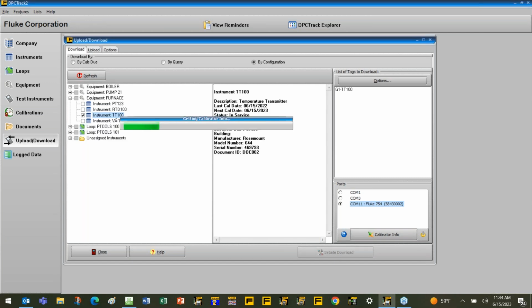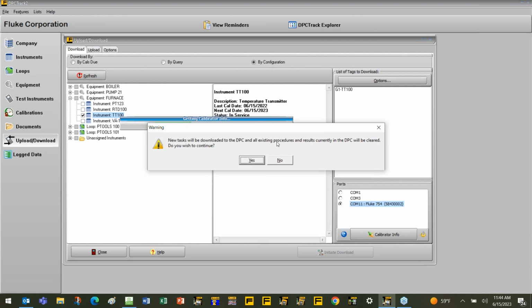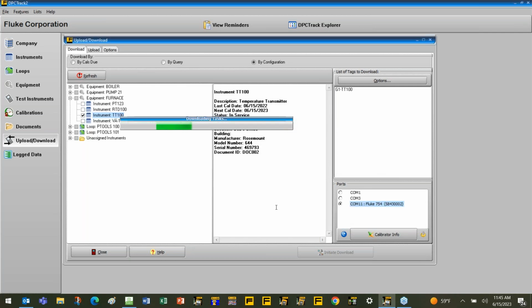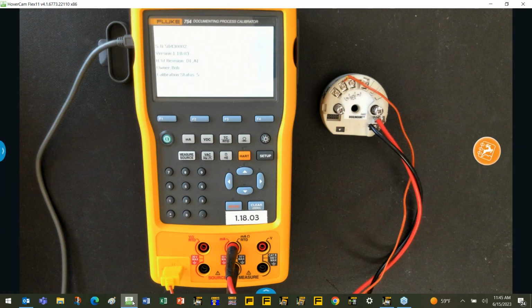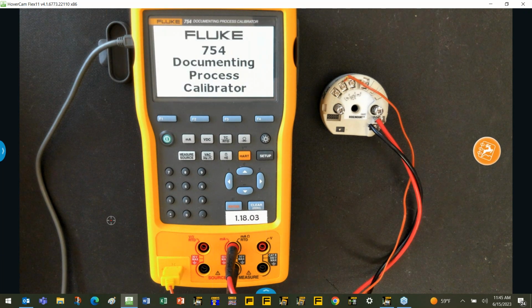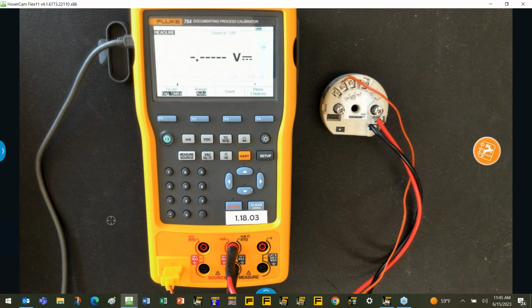And it's going to ask you if you want to continue, since it's going to automatically delete any other records that are on the calibrator. So we're going to continue that. And while that's downloading, I'm going to switch screens and bring up the Fluke 754. And you notice going through, it's getting the download, it's getting stuff deleted, and then it's going to follow through and download from the software the task that we want to perform.